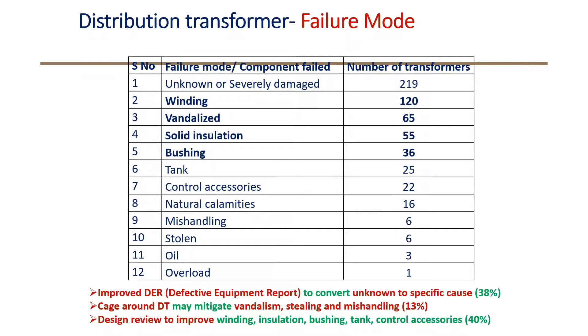Now the failure modes. Of the 12,000 transformers, we found that unknown and severely damaged were 38%. That means the reason is unknown, or the transformer is damaged to an extent that we cannot investigate the failure mode. What is the way out? We are missing good information, so the utility should improve the DER, the defective equipment report, so that some clue can be taken from the DER and this unknown converted to a specific cause. Then winding: the maximum failure in the distribution transformer was due to winding. Then you have vandalism, solid insulation failures, and bushing failures, and other accessory failures are fewer.